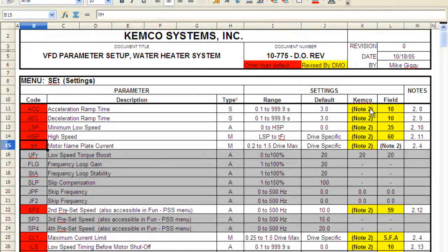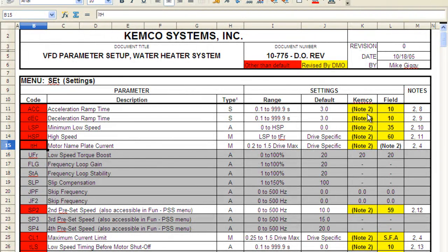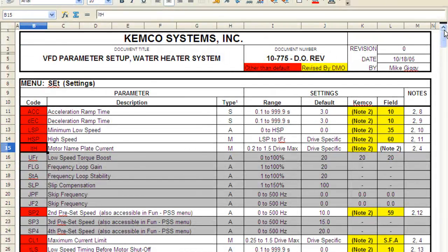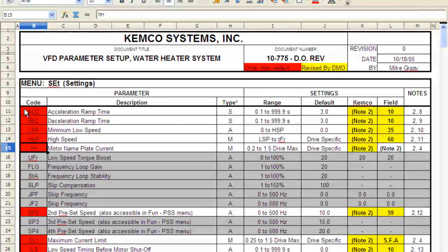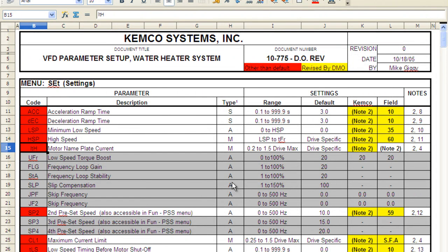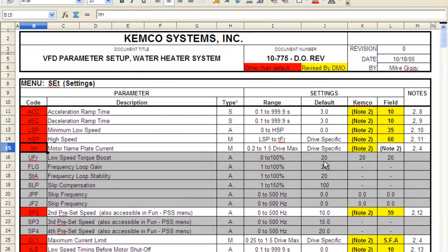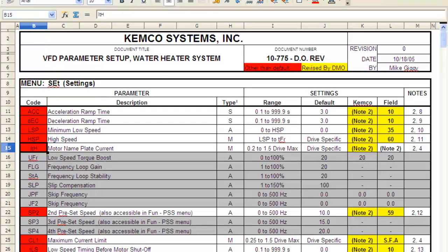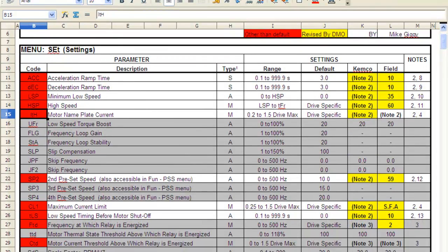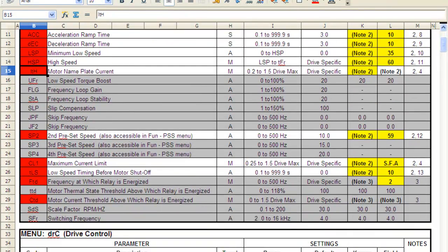So below this procedure, if you see note, it tells you what you need to make that decision. And of course Kemco will help you do that if you need help on that. But if you reset the drive to default, go back in and change all these red permissives. Skip all the other ones because they don't need to be changed from factory default, which is outlined here. It says the default is 20 on this permissive, Kemco is 20, so it's grayed out, meaning you don't have to change it.